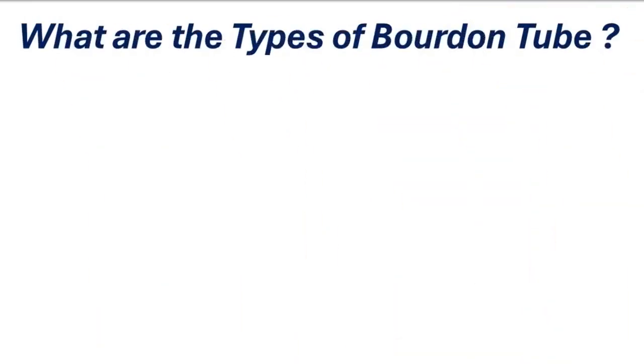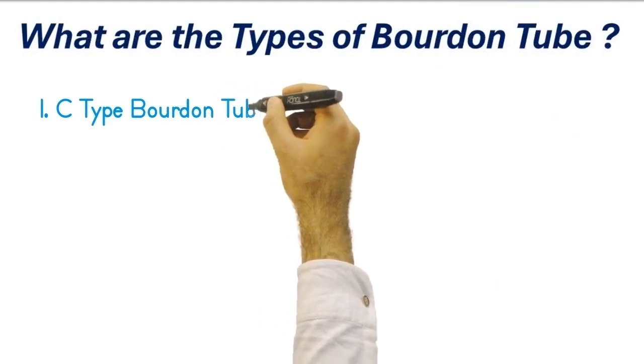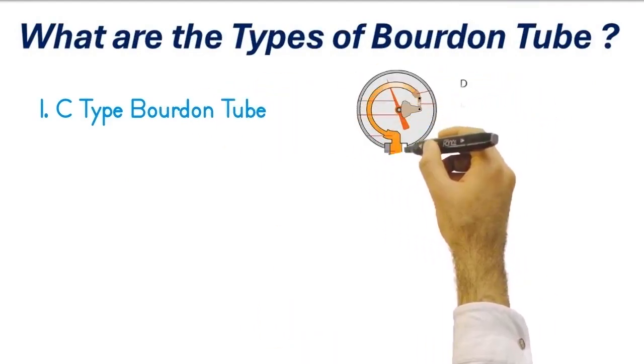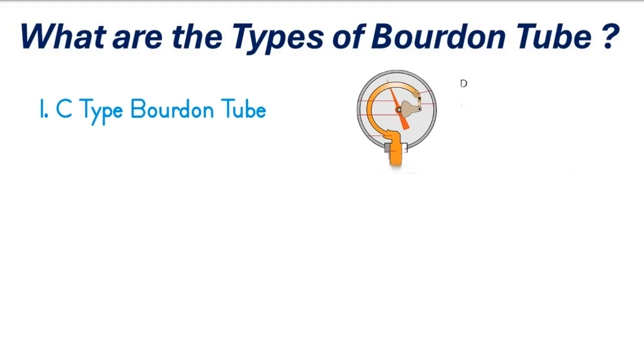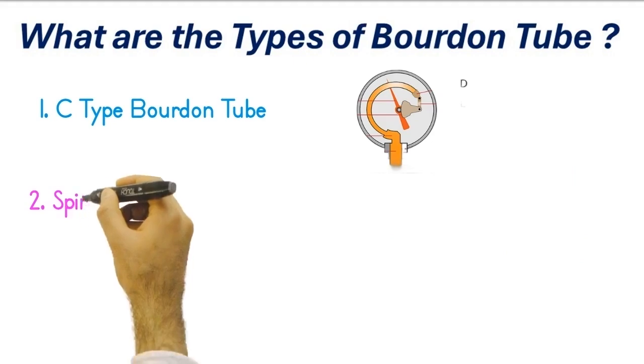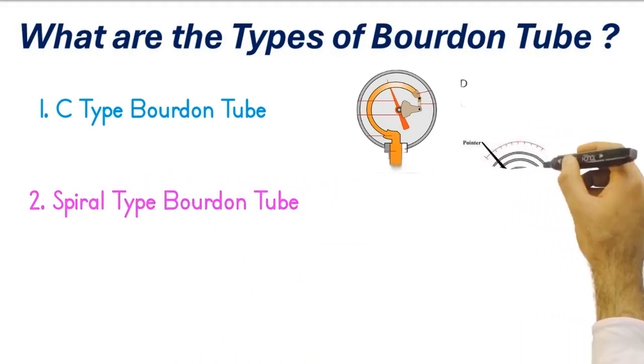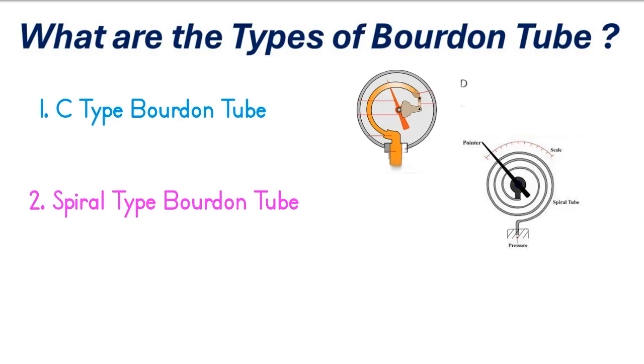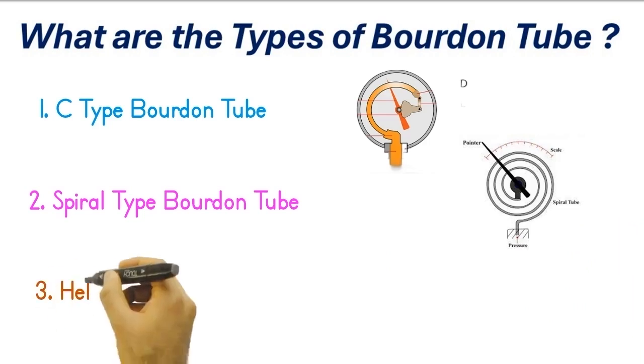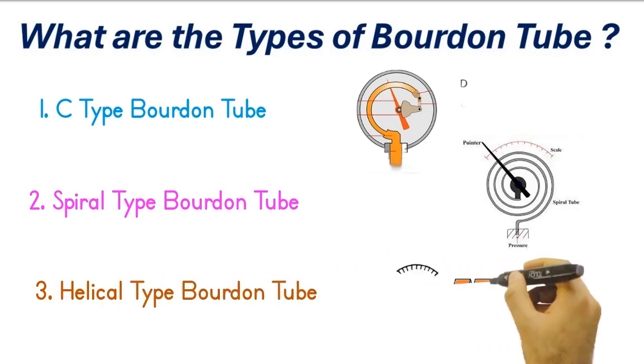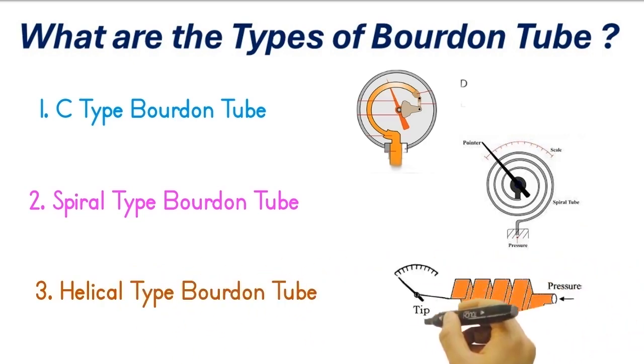What are the types of Bourdon tube? There are three types. Number one: the C-type Bourdon tube, which is the most widely used and is used for medium to high range pressure measurement. Number two: the spiral-type Bourdon tube, used in rugged industrial environments where mechanical stress and vibration are common. Number three: the helical-type Bourdon tube, suitable for applications requiring precise pressure measurement, like laboratories.